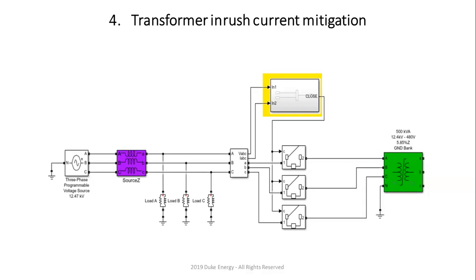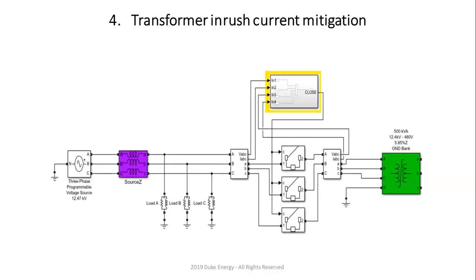Every time you do some kind of a scheme or testing on a system, you've got to do reliability testing to make sure that stuff trips when it's supposed to trip. But then you have to introduce all of these temporary faults and all the other stuff and make sure you don't trip on transients. And then the last one that we have tried, what's currently available on the market with respect to the controllers, is using residual magnetism, right? And we have actually implemented a couple of those, right?